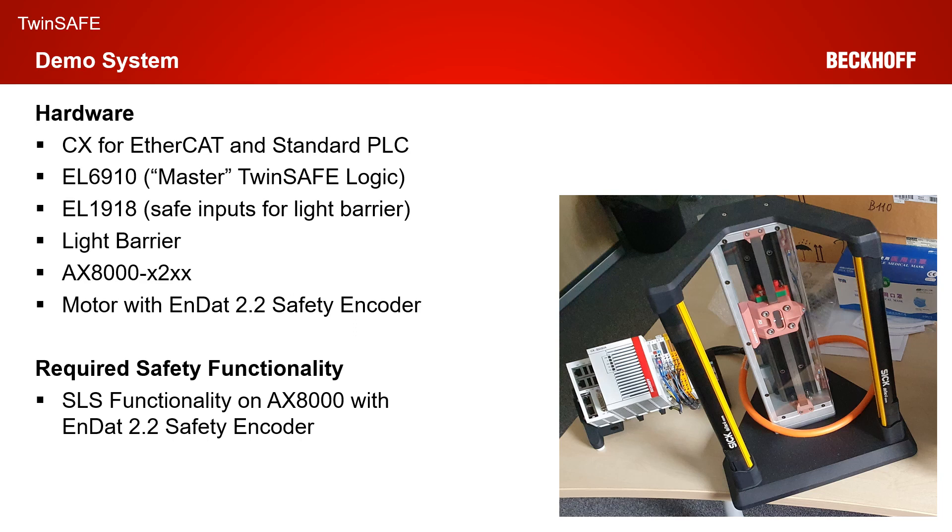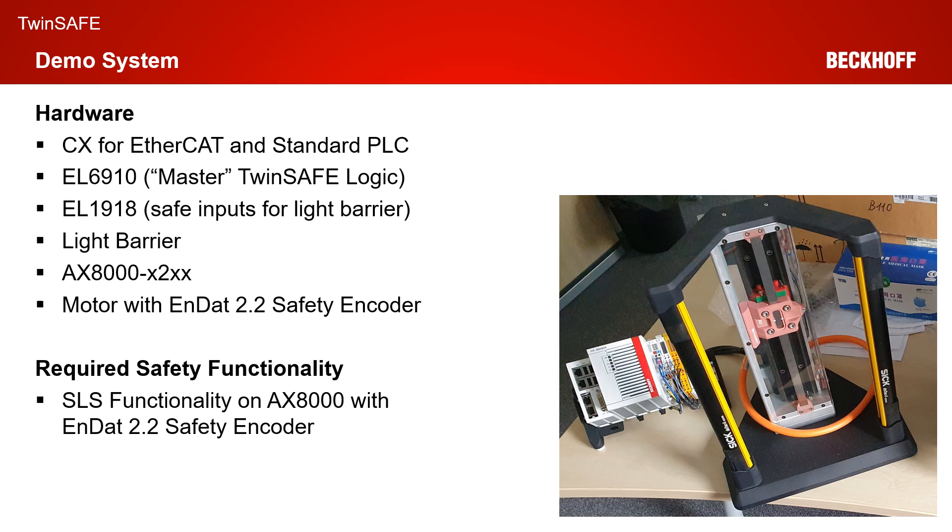We have an AX8000 in the X2XX safe motion version and for today we have a motor with EnDat 2.2 safety encoder integrated. The required safety functionality today is we want to trigger a safe limited speed functionality on the AX8000 via the EL6910 communication and the AX8000 should use the signal of the EnDat 2.2 safety encoder for the SLS functionality.